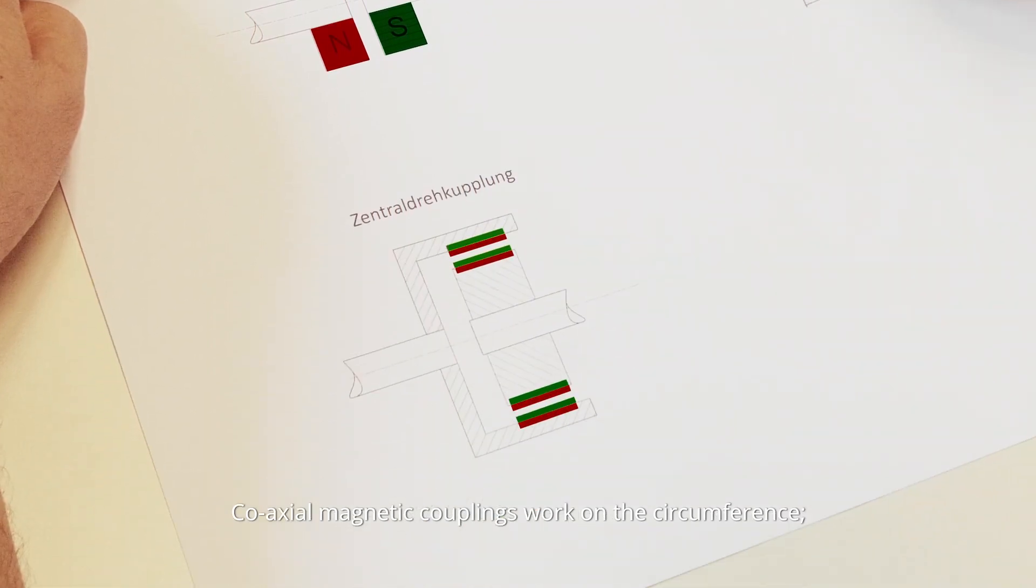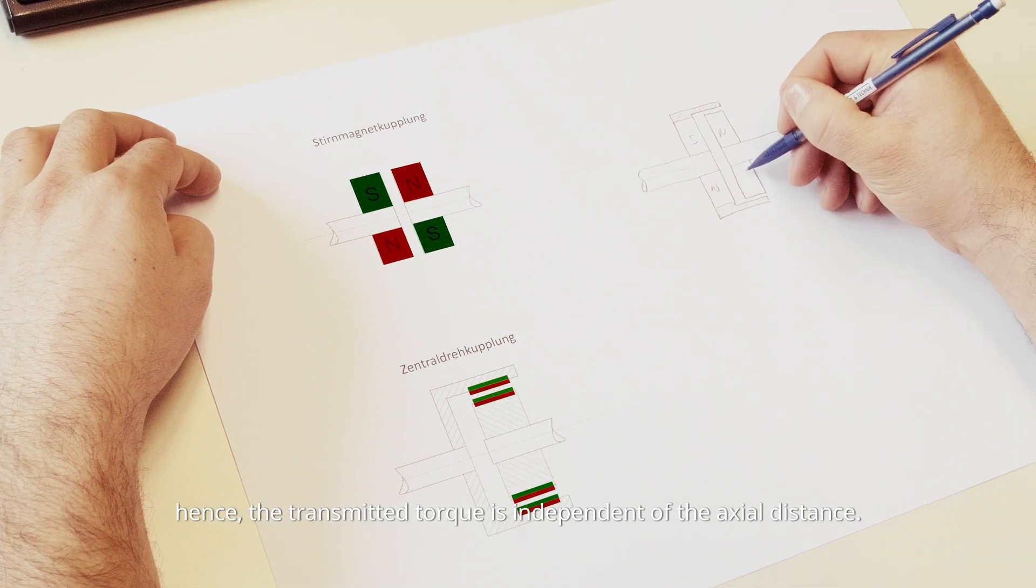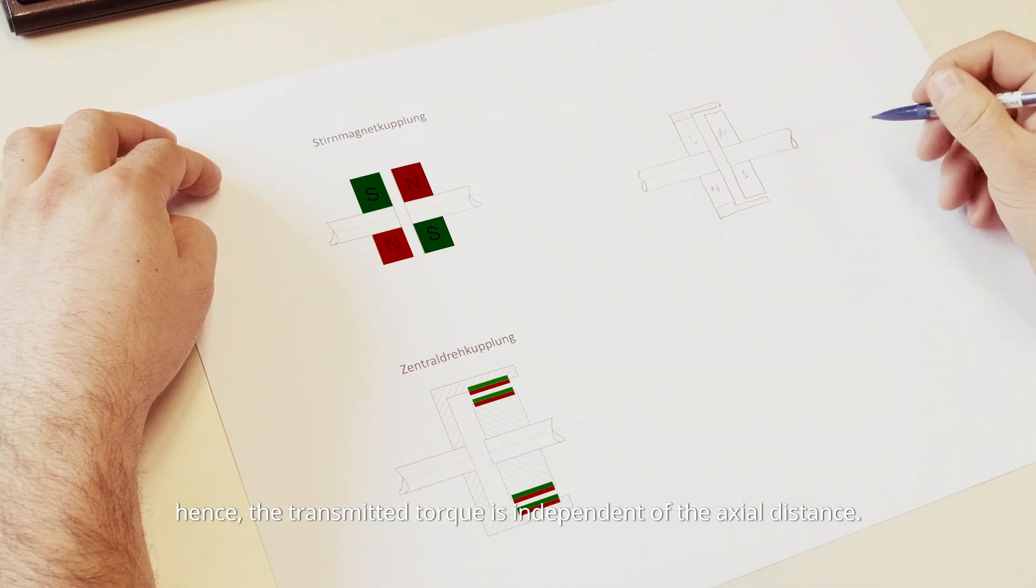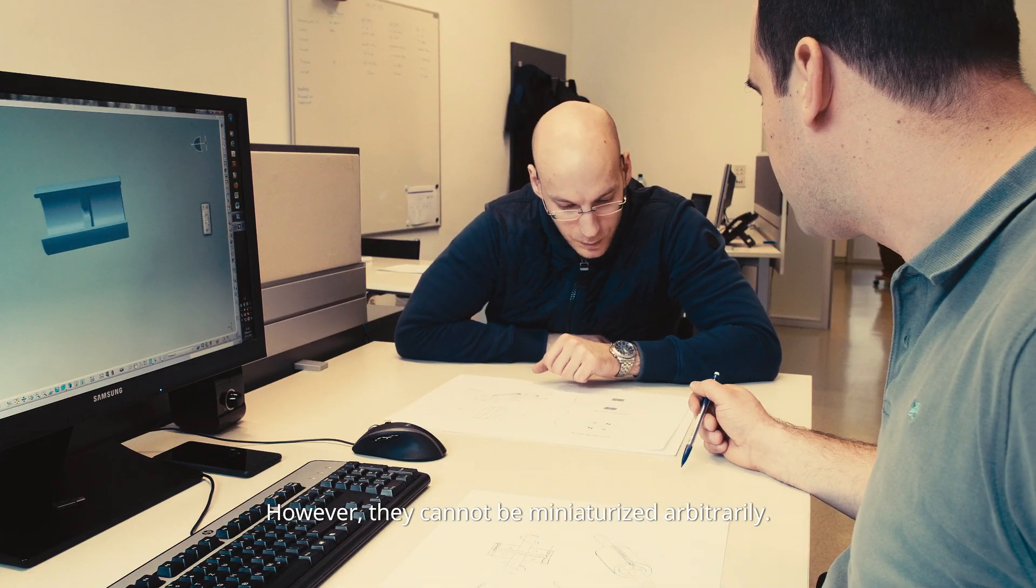Coaxial magnetic couplings work on a circumference, hence the transmitted torque is independent of the axial distance. However, they cannot be miniaturized arbitrarily. The transmission capability becomes reduced with the miniaturization of the magnets.